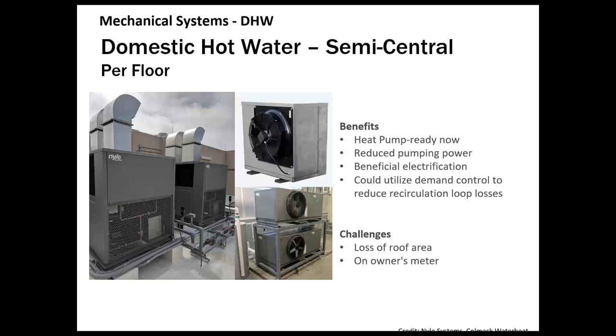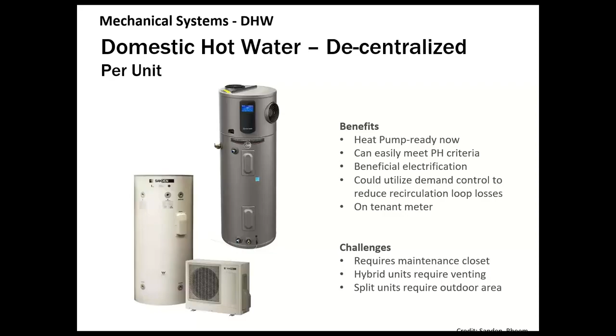As an alternative on the decentralized systems, gas-fired units are not allowed in Passive House within residential spaces. And so the alternative really is electric storage or heat pump type systems or instantaneous electric, but I won't get into that. But here are two different heat pump type systems that would be on a tenant's meter, and again, easily meet the Passive House criteria and are heat pump, so very efficient type systems. They do require a maintenance closet, and the hybrid type units like the Rheem that you see in gray require venting as well. A split type system like the white one from Sanden does require outdoor area for that outdoor condensing unit, but the indoor storage tank does not require any special venting.